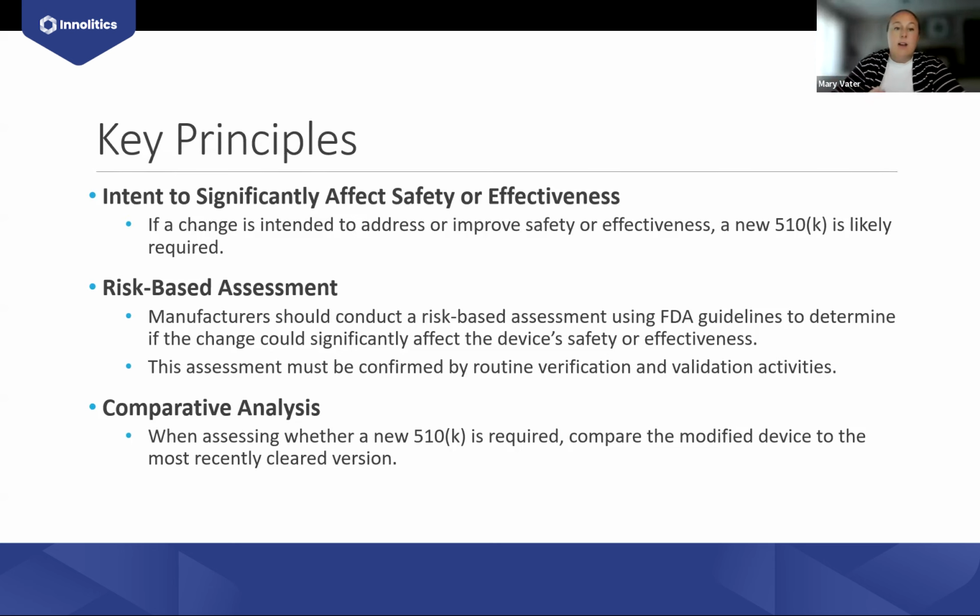And then also, if there are new risks, or if you are significantly changing the risk profile of the device, or making a change to the functionality, then regardless of whether or not it's a 510K or a letter to file, you still need to do the necessary V&V activities associated with evaluating that change. So that's typically a really important part of the letters to file, is that you have adequately tested the change to ensure that it's meeting your requirements and not introducing new risks that weren't anticipated.